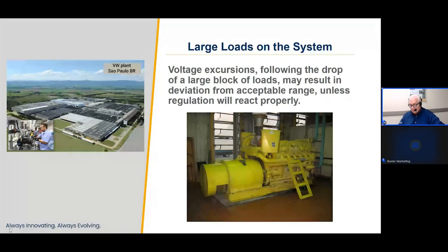This was not an outage caused by short circuit faults or open transmission line faults. The excursion of the line voltage above the tripping point following the shutdown of the VW plant set the local outage in motion. These two events were not simply coincidental. The rise in voltage, high enough to trip, was caused by insufficient dynamic response of the voltage control systems on the part of the utility. This event was caused by poor voltage regulation. The network did not properly respond to the disturbance of losing a large block of loads. Instead, poor control aggravated the event by triggering the drop of combined loads of the supermarket.